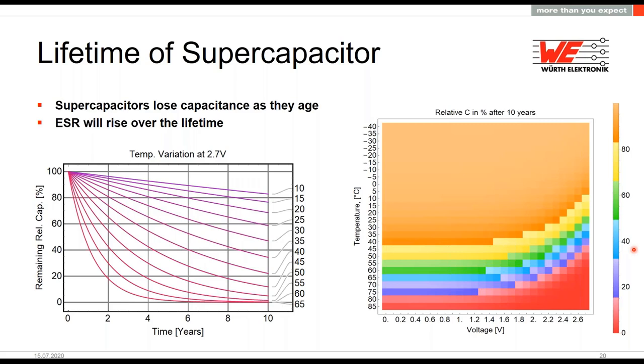Regarding the lifetime diagram: the Y-axis on the left diagram shows the remaining relative capacitance. For example, at 40°C after 10 years you have 20% of your initial capacitance remaining — so if you started with 10 farad, you'd have 2 farad at the end. The bar chart on the right shows the same information — remaining relative capacitance in percentage — just in a different visual format.